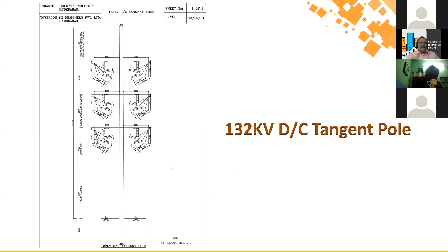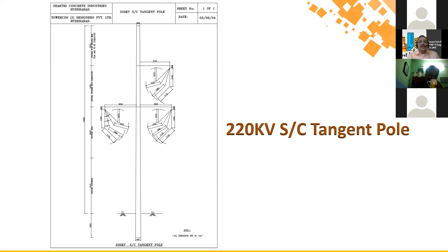And this is a tangent pole, incoming power for this. We designed these poles also. I said 132 kV double circuit pole and 220 kV single circuit tangent pole. All this we have designed. And 132 kV single circuit tangent pole and 132 kV double circuit suspension. So you can see these are the insulated cross arms. So we have developed the standard details for these poles. These are all spun concrete, pre-stressed spun concrete poles.